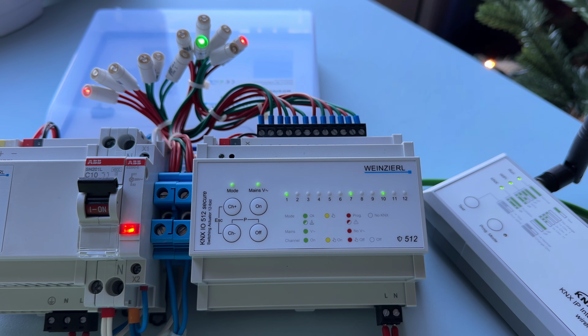I mainly use the KNX IO 512 in projects with exterior lighting, where the loads are switched through contactors. And because those contactors usually serve the same line and neutral, this device fits perfectly. But in cases where each load needs power from a different breaker, I'll go with an actuator that provides a dedicated terminal per output. If you have used this actuator before, let me know your experience in the comments.